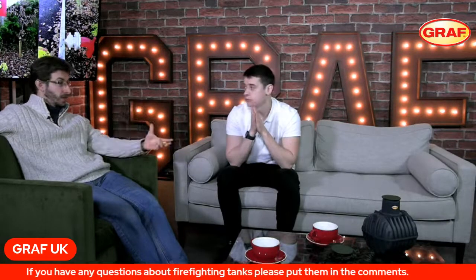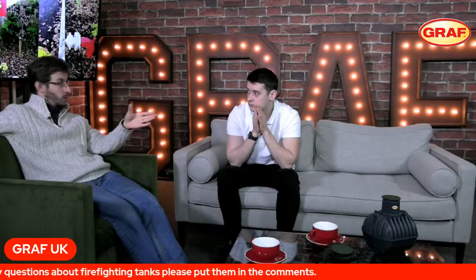It's quite right as you said, Callum. We always need to ensure we have the tank volume available to us. Most enquiries start when we talk about firefighting tanks with somebody asking that exact question: can I use rainwater for my fire solution? Now you can, but you need to ensure that you've got that tank volume available should the emergency event happen. And if you were to have consecutive emergency events, you need to ensure that the tank is topped up in that time frame. And if you're waiting on a rainfall to happen, that may never have happened. So it's up to the emergency fire services to refill that tank.